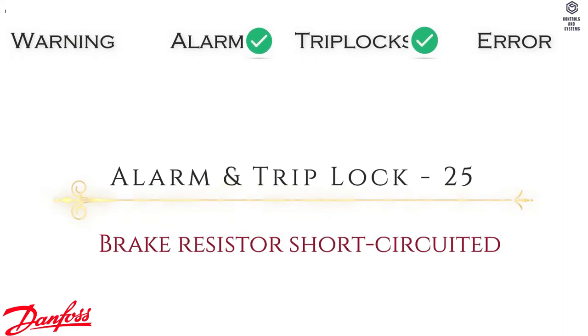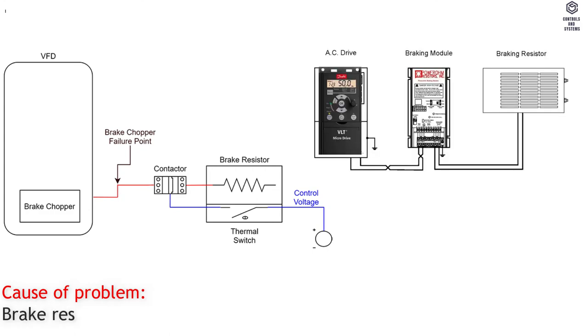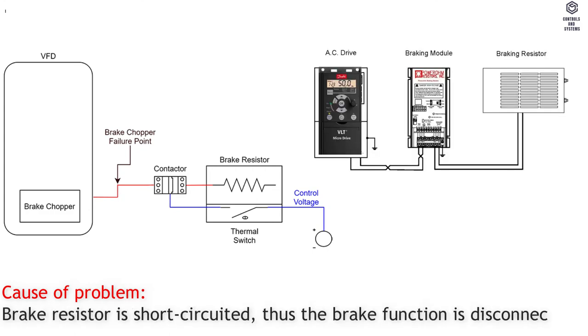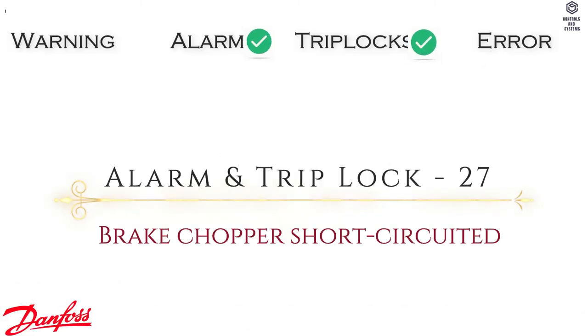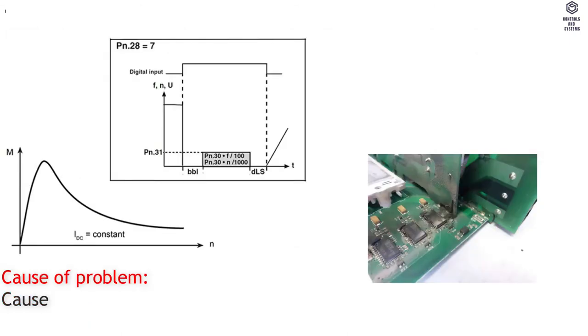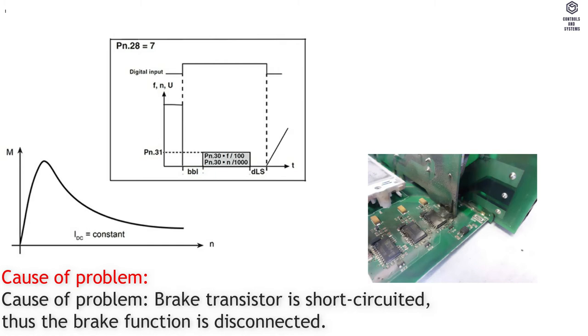Alarm and Trip Lock 25: Brake Resistor Short Circuited. Cause of Problem — brake resistor is short circuited, thus the brake function is disconnected. Alarm and Trip Lock 27: Brake Chopper Short Circuited. Cause of Problem — brake transistor is short circuited, thus the brake function is disconnected.